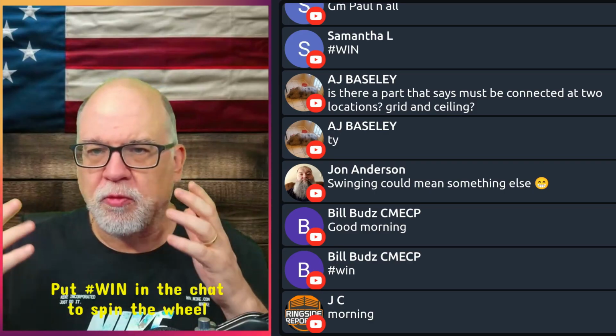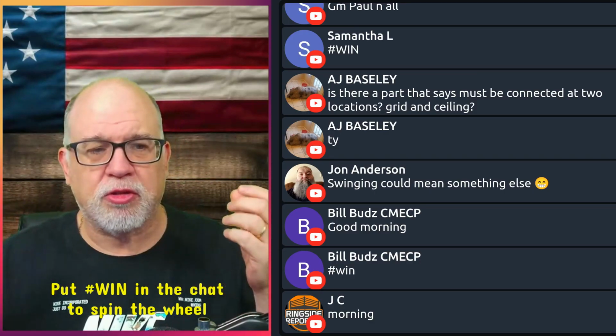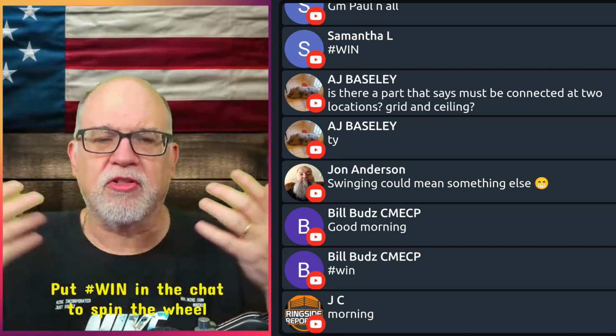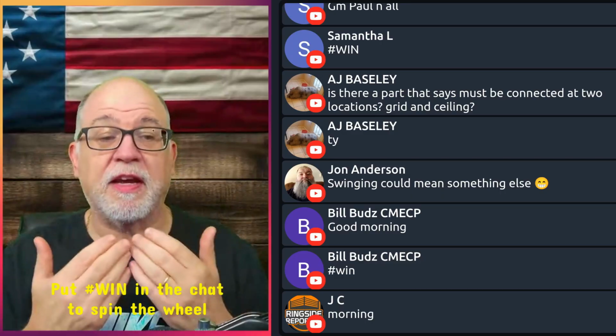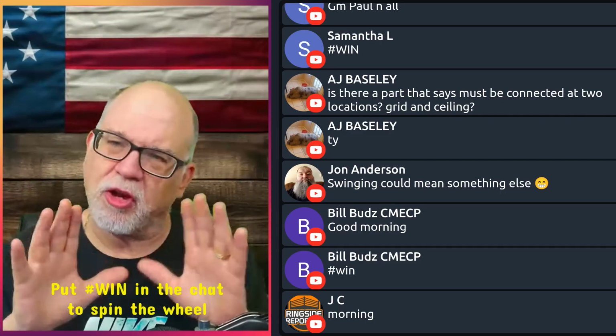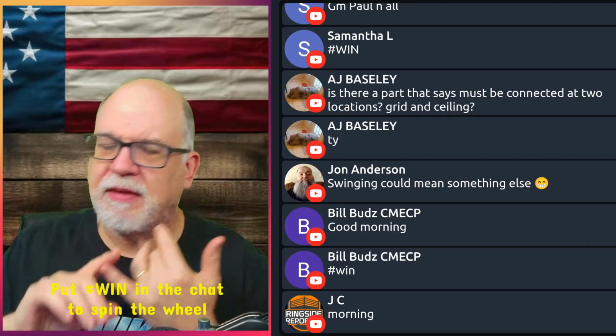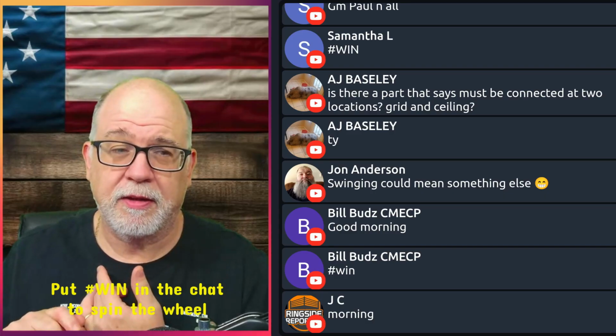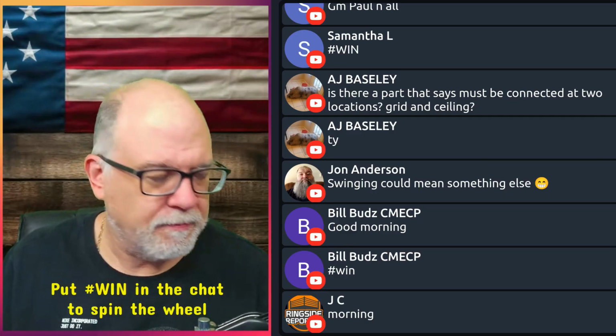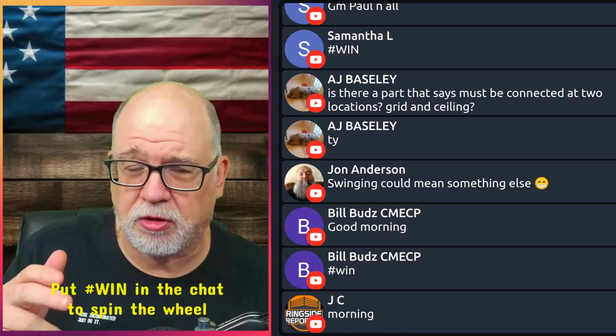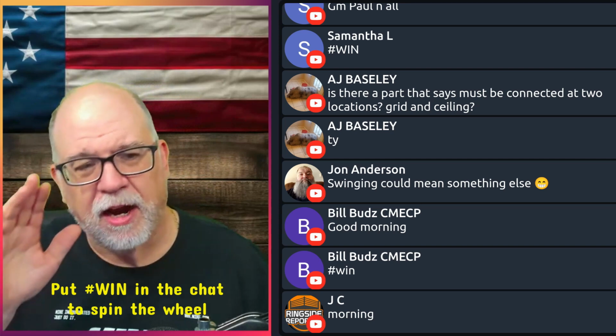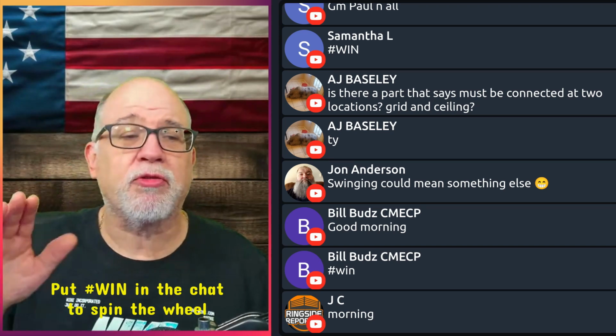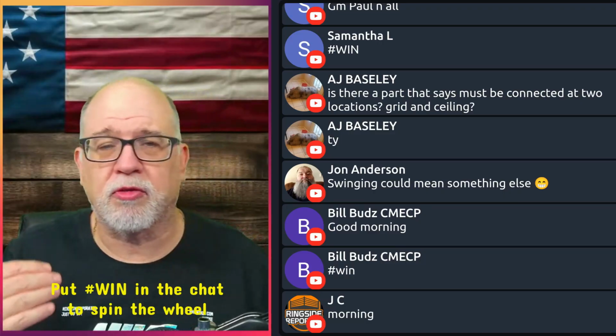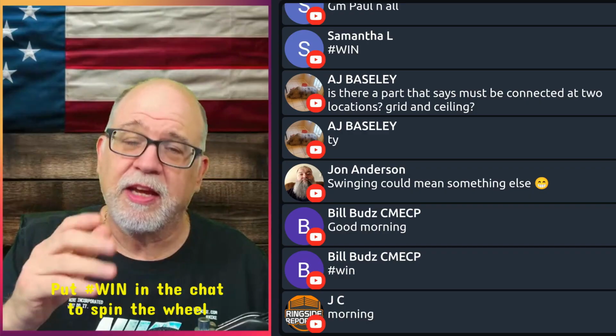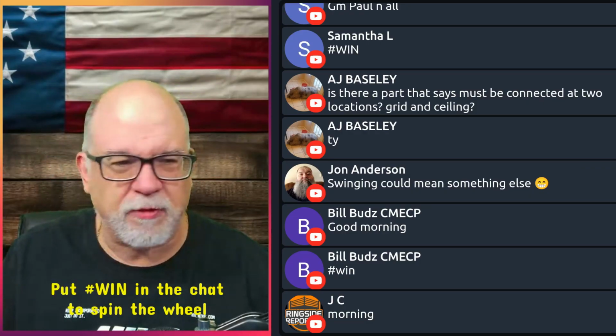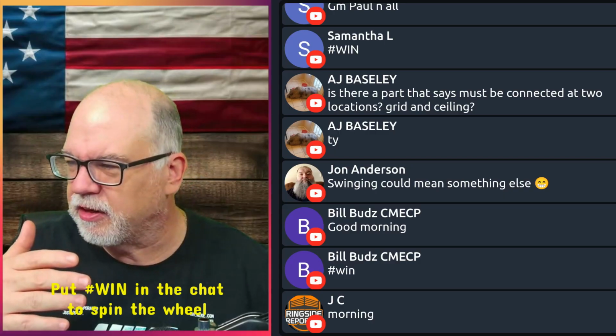So it didn't matter in those pool rooms or those areas or in the ground, because you're bonding at each end through the fitting. Even if it broke somewhere in there, it's still going to be bonded at the system, because you've got an equipment ground that's going to connect to those boxes to ensure that path. So it wasn't that big of a deal. And so the PVC material is most certainly resistant to corrosive conditions if it's not damaged during install. As an inspector, one of the things we would look for is whether the PVC material is damaged, if you scuffed it up. So be careful on your install. But again, PVC material is very resilient, and people misread the code in 680. They don't understand that the manufacturers who produce that product already know that PVC, in its thickness, is very resistant to corrosive conditions or anything like cinder fills, alkalis, chlorides, and hydrochloric acid.